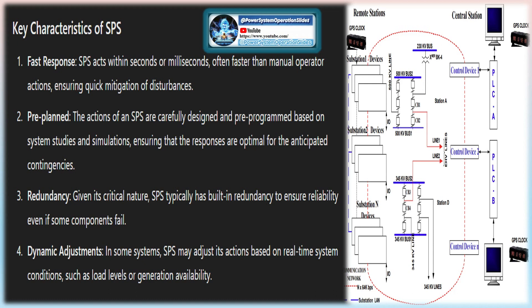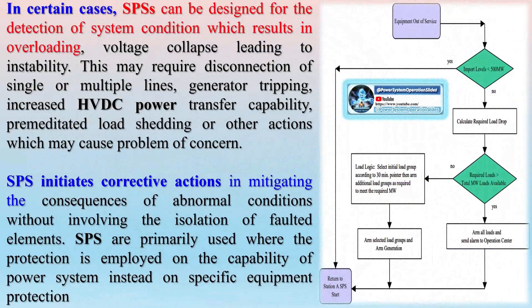SPS initiates corrective actions in mitigating consequences of abnormal conditions without involving the isolation of faulted elements. SPS are primarily used where protection is employed on the capability of the power system instead of specific equipment protection. SPS are designed to take special action in response to event disturbances such as transmission faults, cascading outage of lines, generator outages, sudden large load changeovers, and HVDC pole blocking.